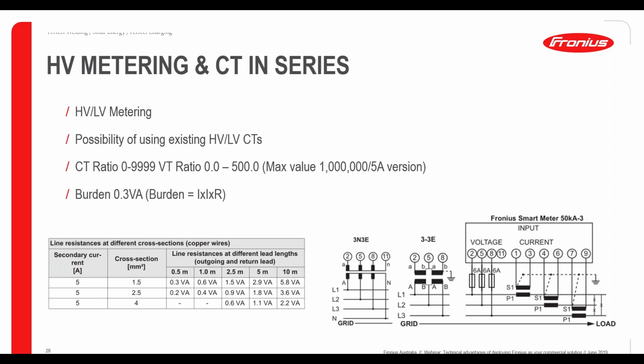What we support here is a VT ratio from 0 to 500 and a CT ratio from 0 to almost 10,000. It's important to note that as this is an accurate meter, the burden that we pose in the measurement circuit is very low. It's 0.3 VA. On the bottom left, we show how the choice of cable size can impact the burden on site. Be mindful that this will also depend on your CT of choice and the class accuracy it comes with. But the point here is it is very accurate and presents very low burden to the metering circuit, and obviously not shown here, it can be used with CTs in series.